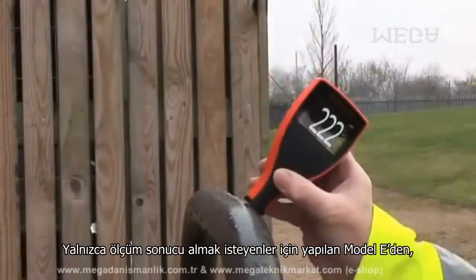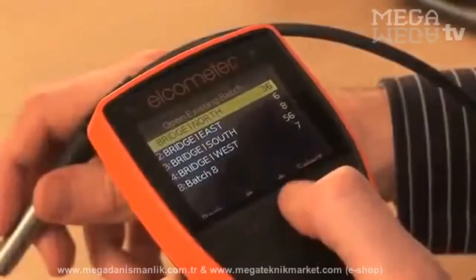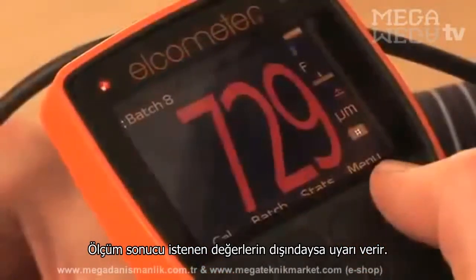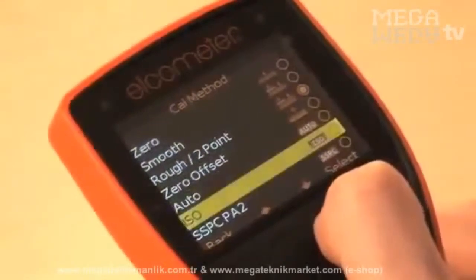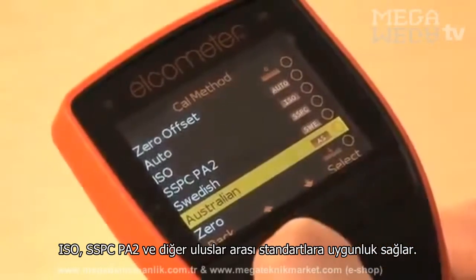The Elcometer 456 is available in four versions, from the entry level Model E when thickness measurement is all you need, to Model T, which provides users with alphanumeric batch memory, warning limits identifying when a reading is outside specification, and predefined calibration methods to meet ISO, SSPC PA2, and other national and international standards.